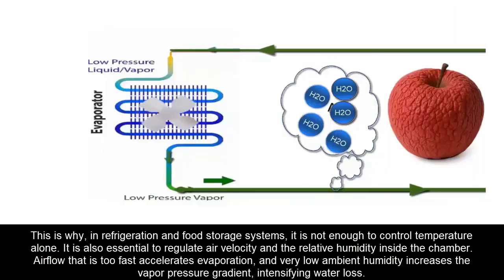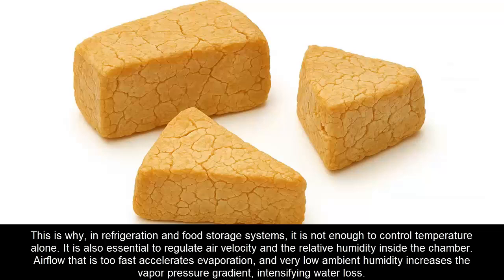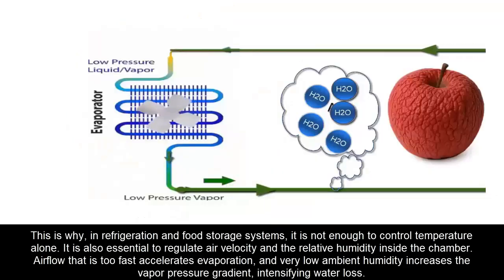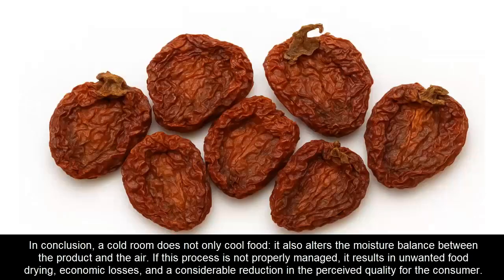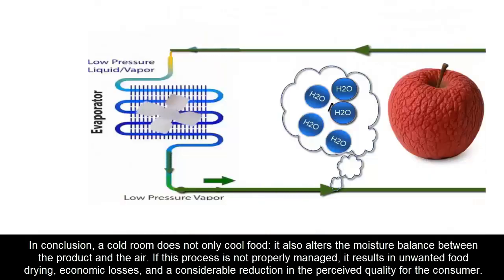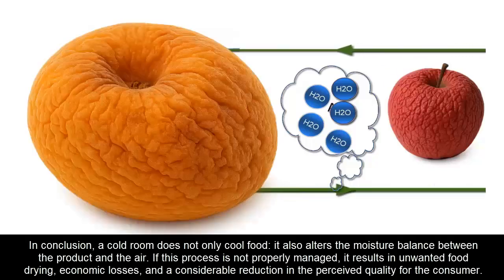Airflow that is too fast accelerates evaporation, and very low ambient humidity increases the vapor pressure gradient, intensifying water loss. In conclusion, a cold room doesn't only cool food, it also alters the moisture balance between the product and the air. If this process is not properly managed, it results in unwanted food drying, economic losses, and a considerable reduction in the perceived quality for the consumer.